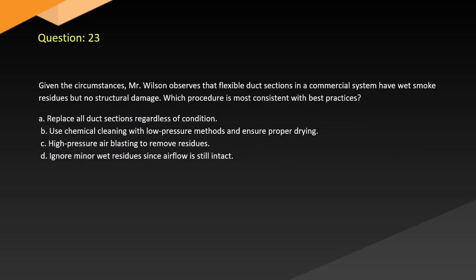Question 23. Given the circumstances, Mr. Wilson observes that flexible duct sections in a commercial system have wet smoke residues but no structural damage. Which procedure is most consistent with best practices? A. Replace all duct sections regardless of condition. B. Use chemical cleaning with low-pressure methods and ensure proper drying. C. High-pressure air blasting to remove residues. D. Ignore minor wet residues since airflow is still intact.